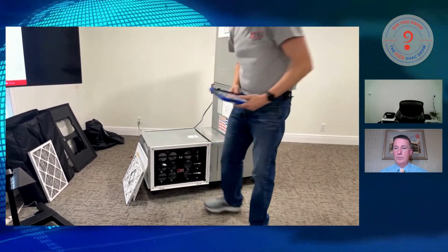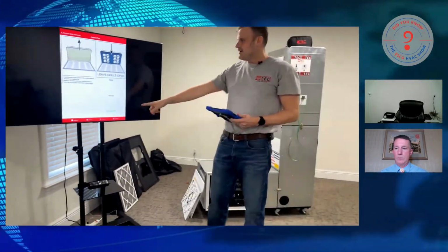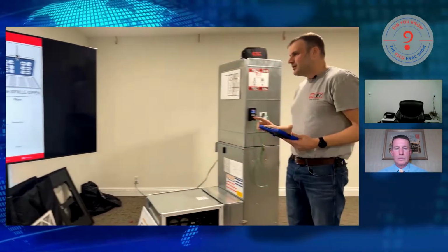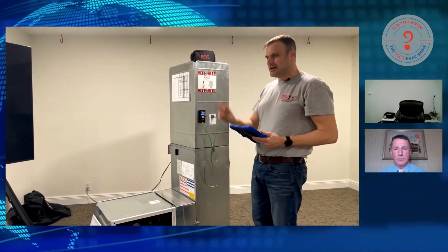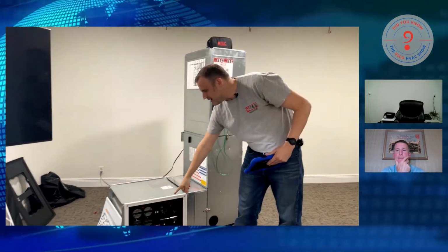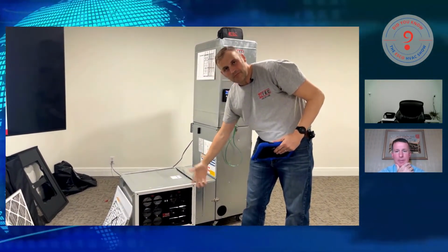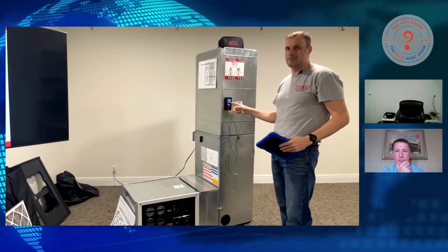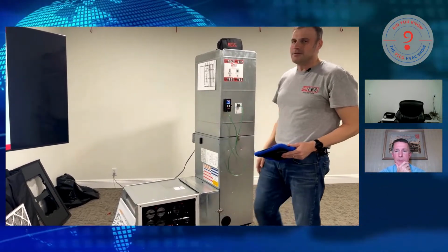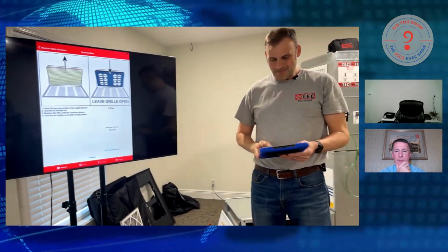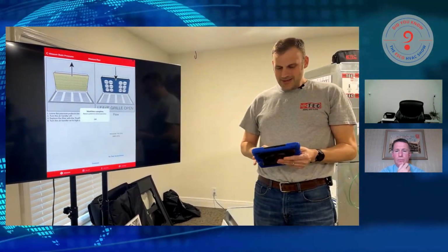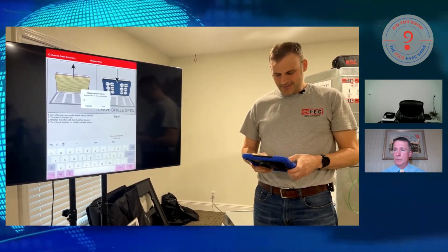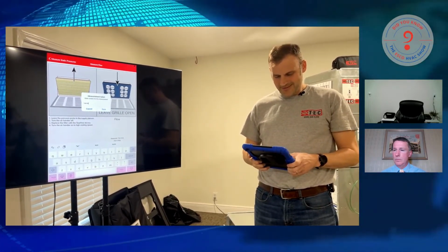Okay? Grid's there. Now, we're going to take a measurement. Once again, just to be clear, it's going to take about 10 seconds to go across that screen. Now, two things are happening right now. We're taking multiple readings at the same time across the grid, about 100 readings, and we're taking about 100 readings in the same location in the supply like we did before. Then we're averaging both. Then we're doing a correction factor. I'll explain that in a second. All right, we've got our measurement. We're going to click continue, workflow complete, and now we can name it. So we're just going to call this lab test, all right?